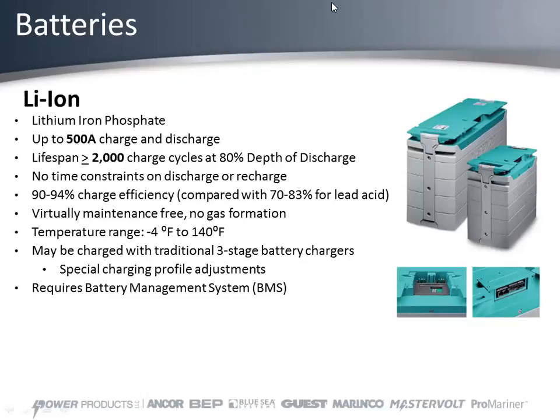The no time constraint means if you have, say, a 200 amp hour battery rated at what we call C20 - you must have seen it in specs - or C10 or C5, C20 being the industry standard. That means the 200 amp hour battery can supply 10 amps for 20 hours. That's what C20 stands for. 10 times 20 is 200 amp hours.